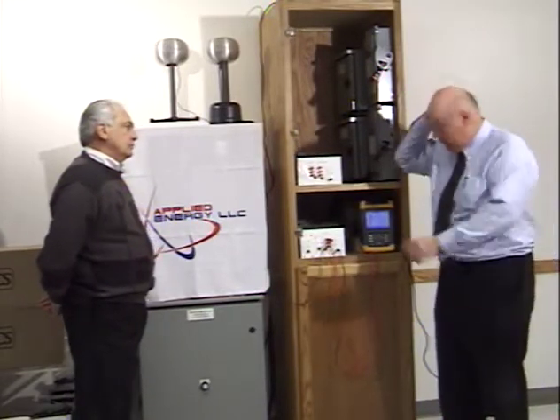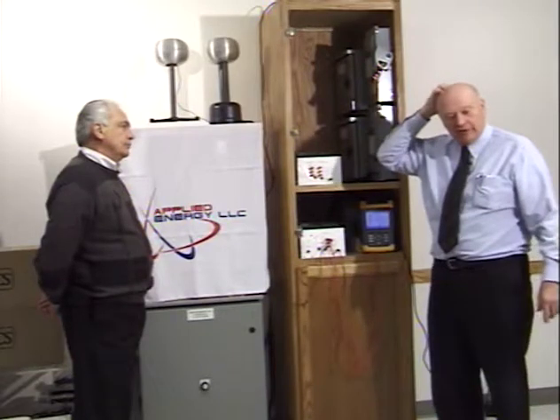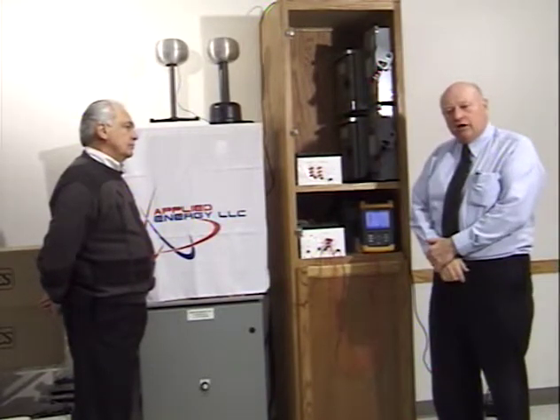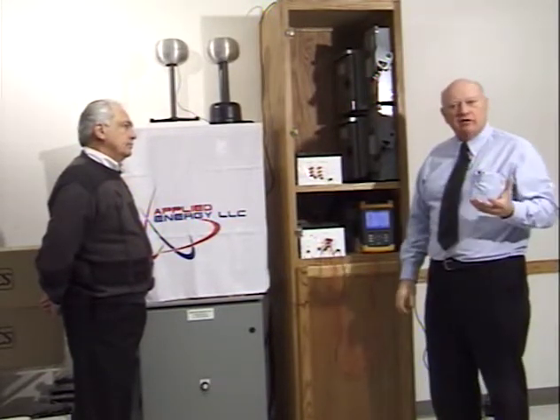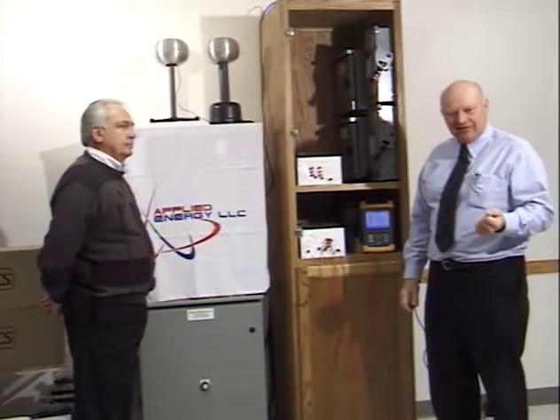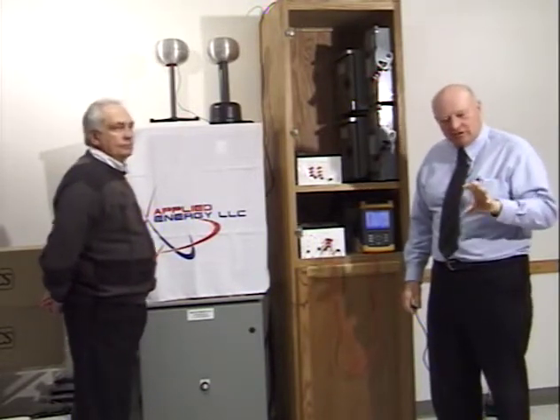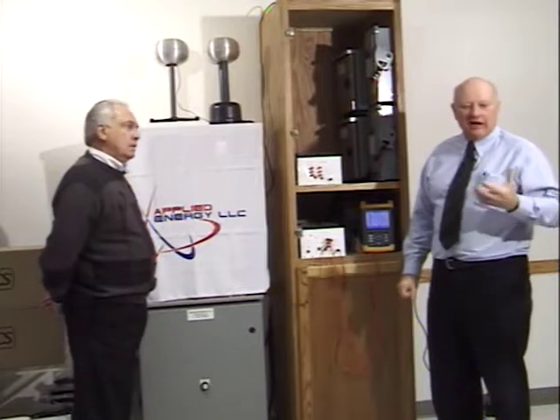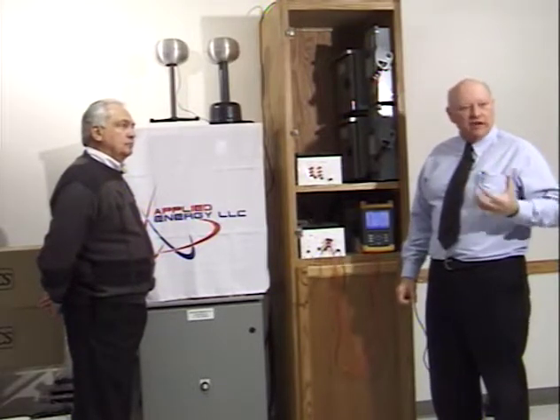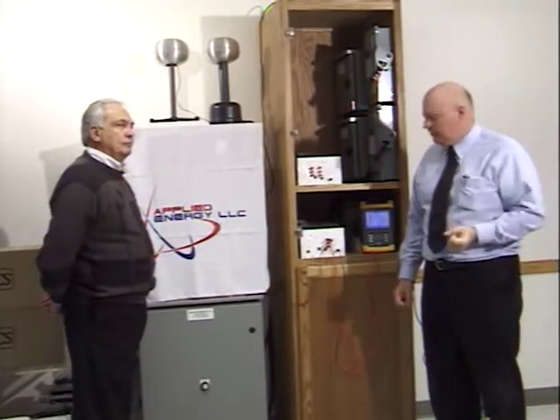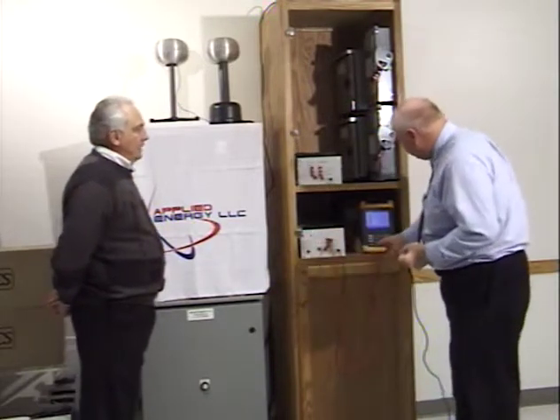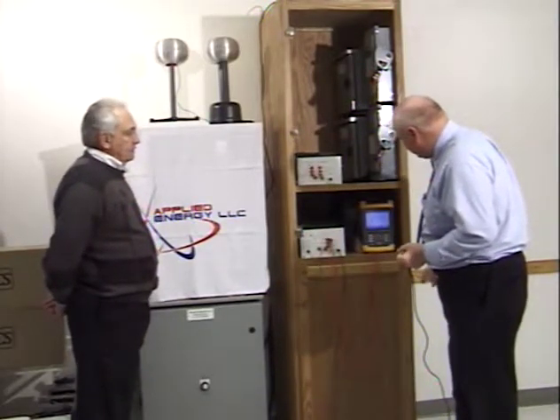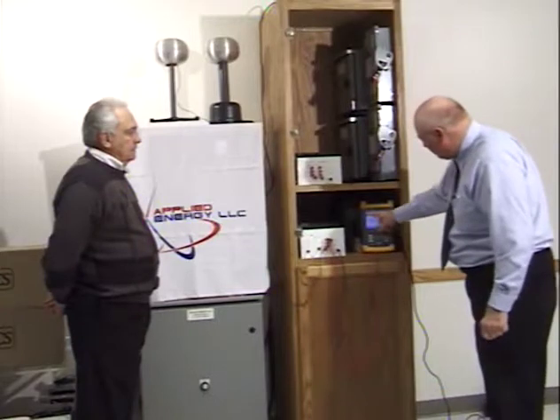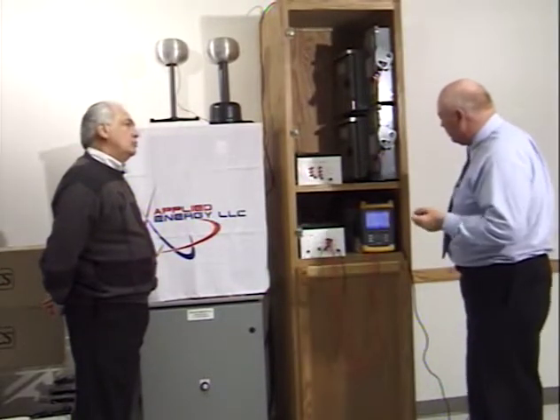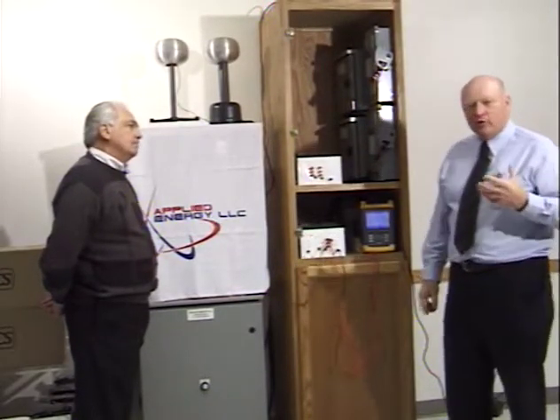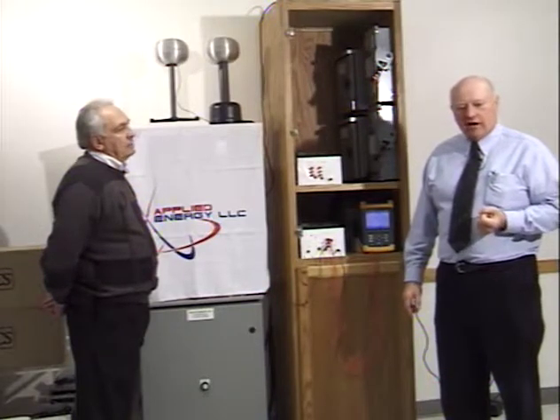Harmonics, we had a significant amount of third harmonic originally. The third harmonic tries to take electric motors and make them stand still. It's a zero sequence, or tries to stop the motor. Well, it obviously can't stop the motor, so it just makes the motor generate additional heat. Now, I'm going to go back to this live scope mode where we have our voltages balanced to talk briefly about transient voltage suppression.